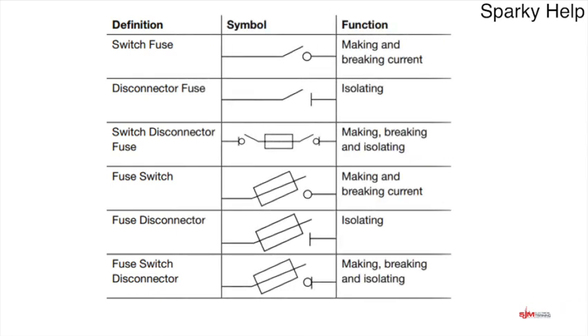We're probably all familiar with BS60947-3, which is the standard that the main switches or isolators we tend to find in there. This sets out the different types of switches that manufacturers can make. It used to be there were two different types of main switch — a switch fuse or a fuse switch, which we can see from the symbols here.